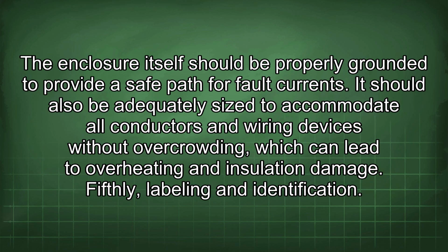The enclosure itself should be properly grounded to provide a safe path for fault currents. It should also be adequately sized to accommodate all conductors and wiring devices without overcrowding, which can lead to overheating and insulation damage. Fifthly, labeling and identification.